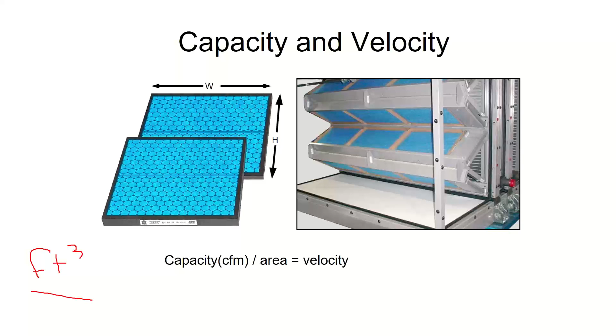As far as the filters go, on commercial air handlers and large rooftops, you'll often see them in this V-bank configuration. The purpose of that is to get me more surface area. If you weren't aware, the CFM, the cubic feet per minute of air, if I write that out as a formula, right, cubic feet per minute is the area, feet squared, times the velocity, or the speed, if you want to think of it that way, the feet per minute, right? So feet per minute times the feet squared is my cubic feet per minute. So the area becomes a big factor.